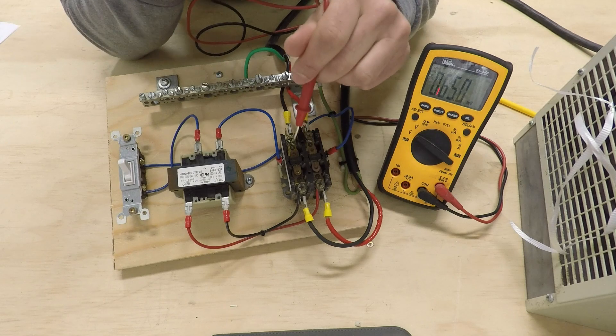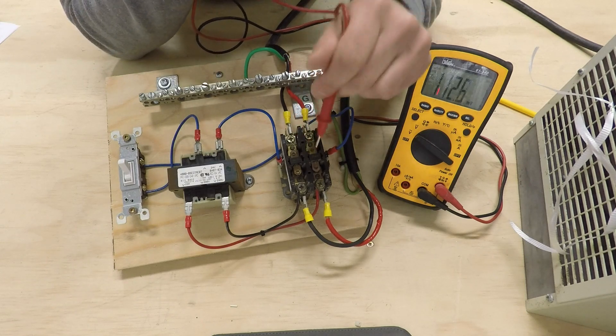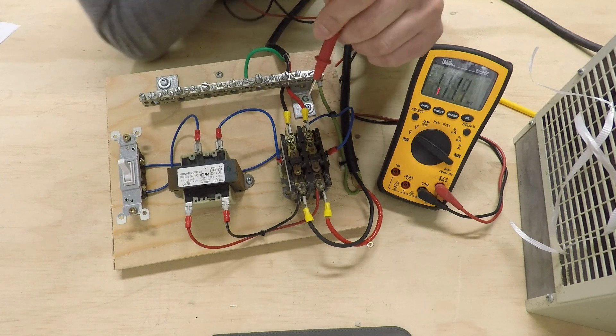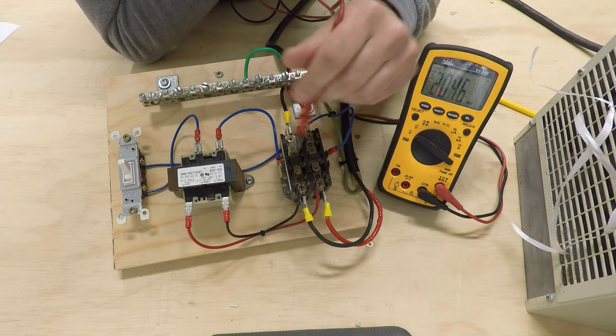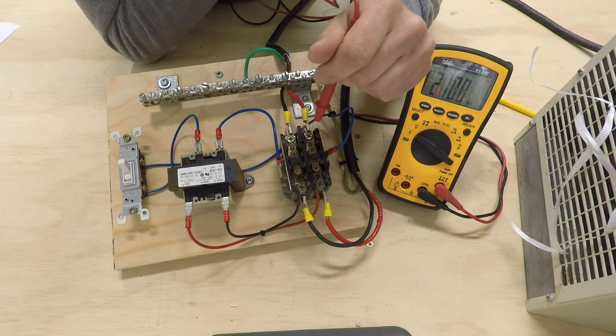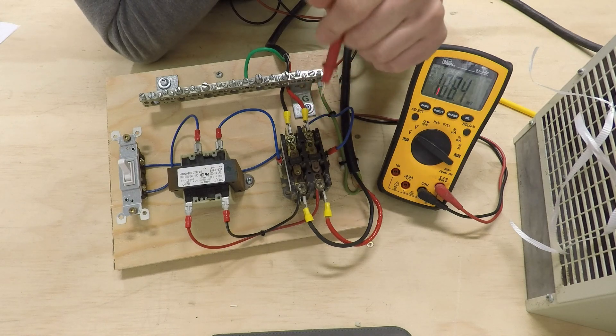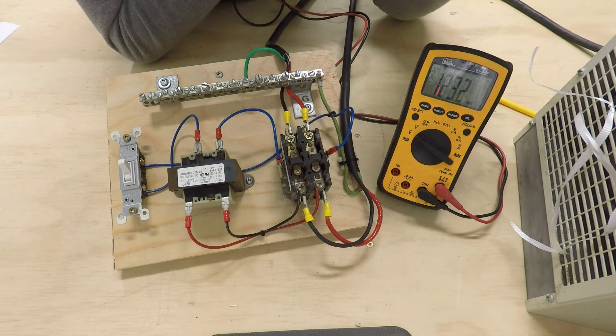So here's the issue. One of these contacts is bad on this contactor. Usually it happens when you get arcing, which causes pitting on the contact surface, or it's just carbon buildup that it's gotten to the point where it actually insulates the connection. And it's not allowing current to flow through the fan and turn it on.